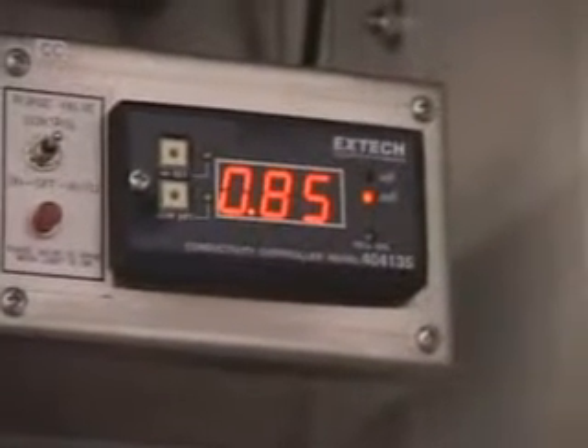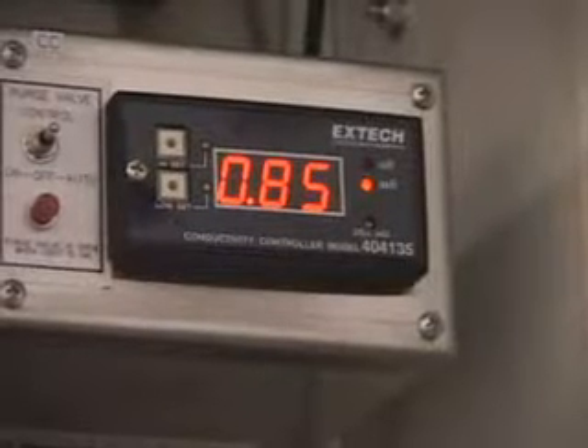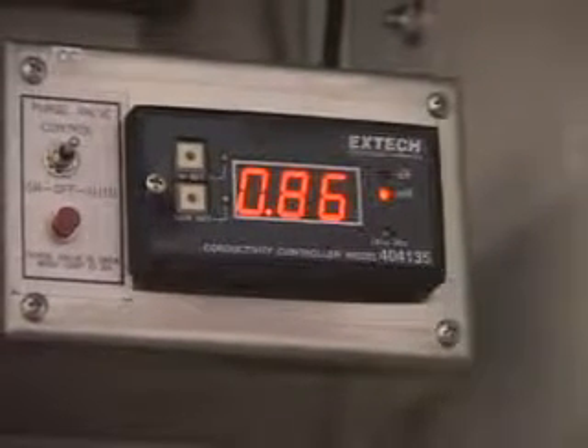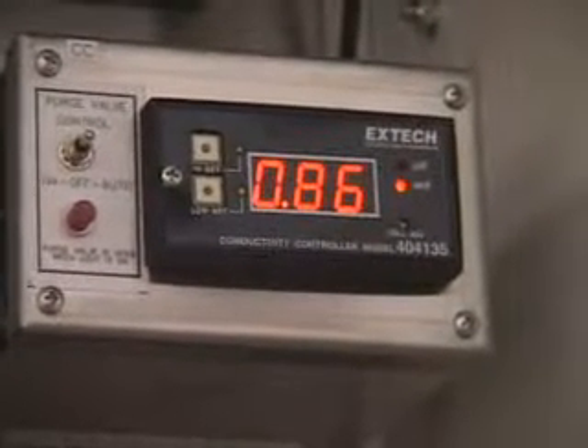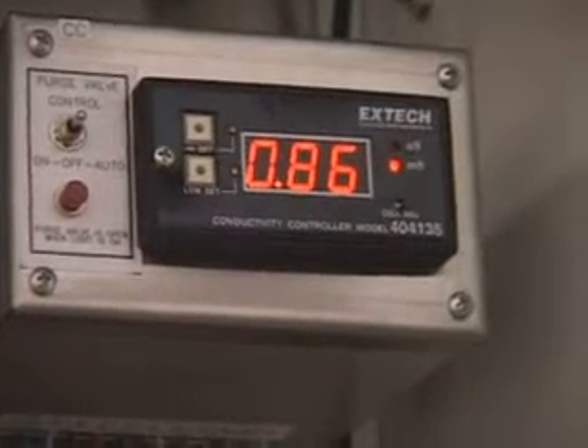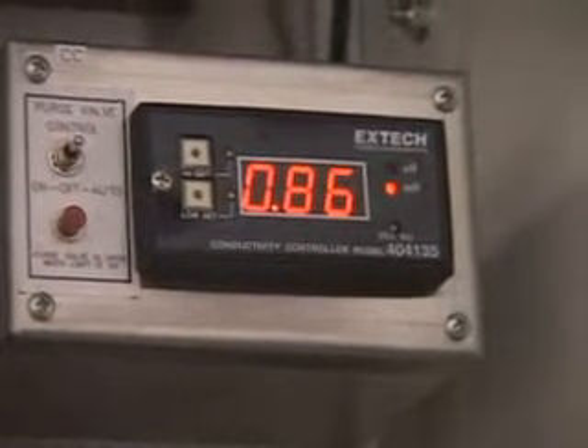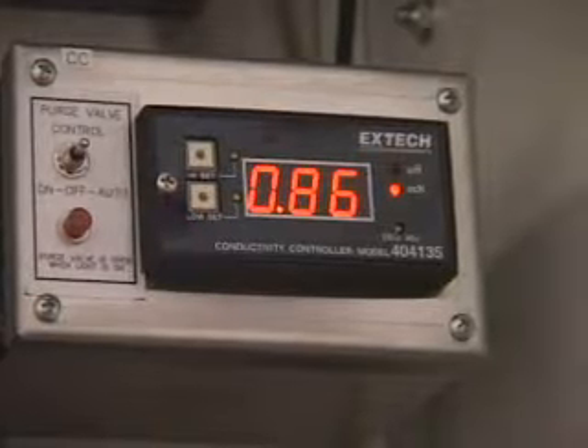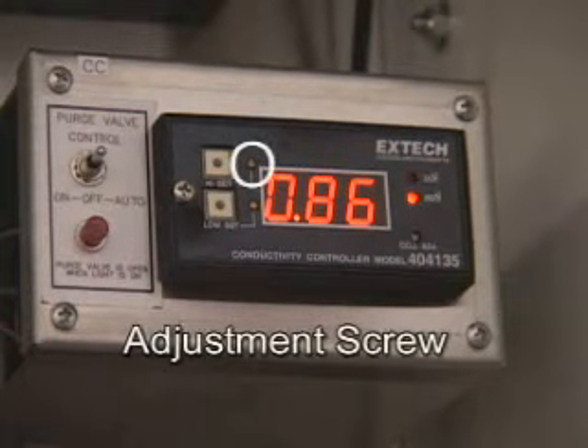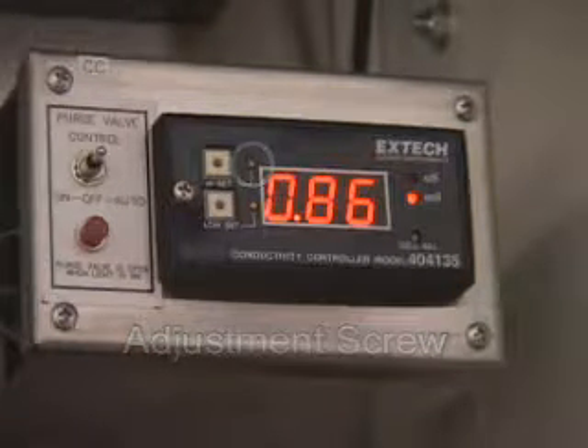It may occasionally be necessary to adjust the conductivity control setting, especially if the water source for the gen changes in quality. This should be done while the water pump is running. This adjustment is made on the conductivity control using the high set button and turning the small screw to change the setting at the same time. Consult the service manual for specific guidance in how to make this setting.